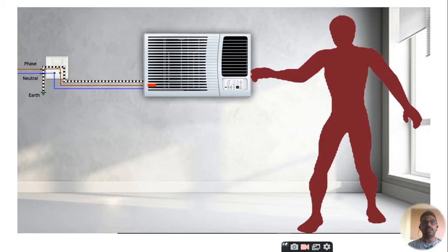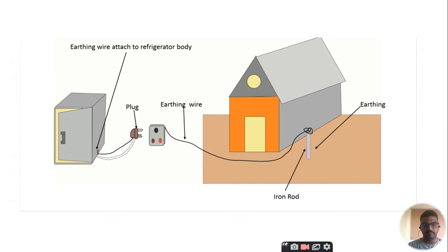But if the earthing is proper at that time, that leakage current will flow through the earthing wire and then it will be neutralized, so that our body will be within the safe limit of the earthing. This is the earth wire attached to the refrigerator body. When you plug it in, the thicker pin of the plug is inserted into the earthing wire, and the earthing rod is connected. So this is one type of earthing mechanism that we have, that is rod type of earthing.